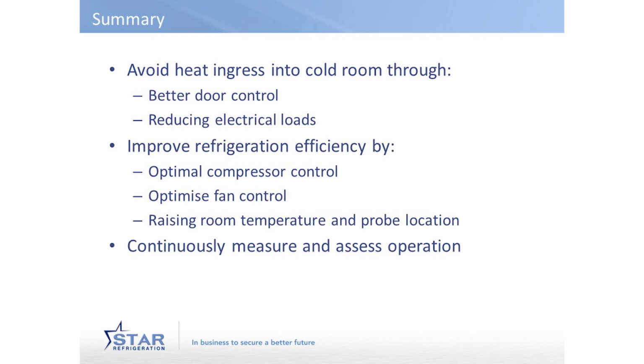So, just to summarise the things we've talked about, minimise the amount of heat load that you're applying to the plant. Better door control is one example. Reduced electrical loads within the space is another. Improve the refrigeration plant performance itself. Once you've minimised the amount of work it has to do, make it as efficient as you can. Look at the compressor control, look at the fan control on the condensers and on the evaporators and in the space, and look at the probe location within the room, and is it really in the best place, or is it making the plant run too much?